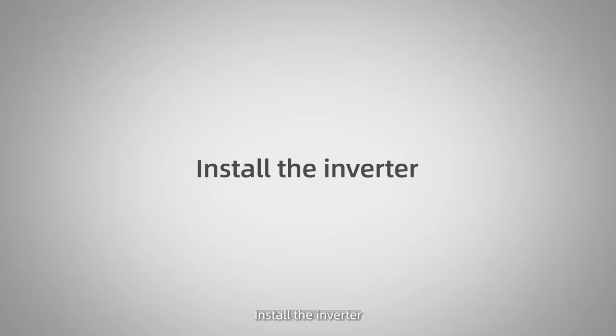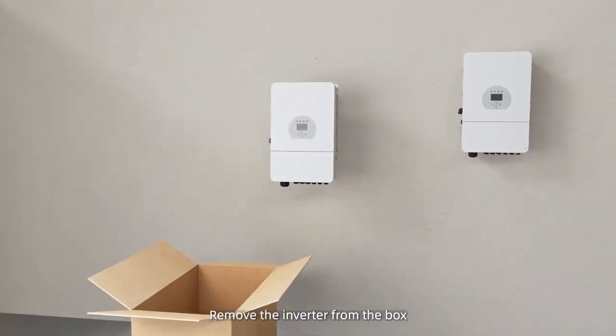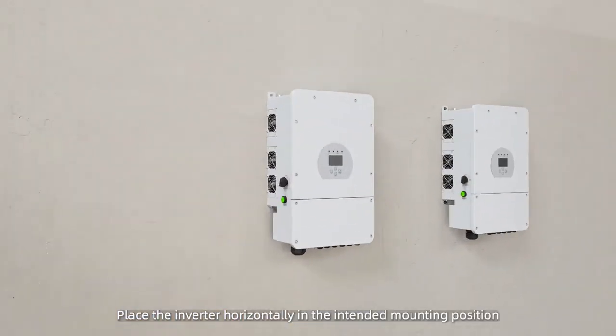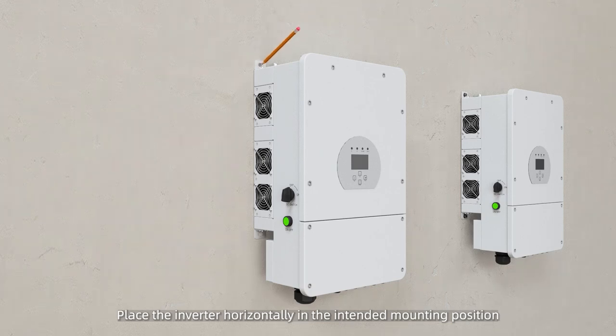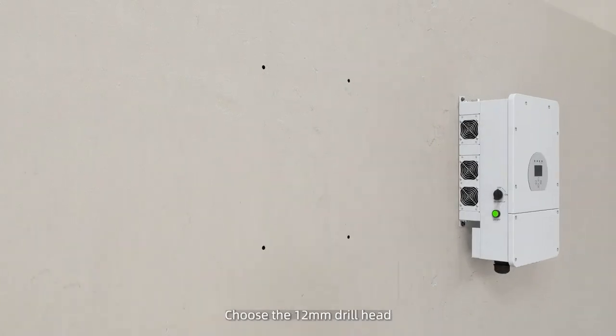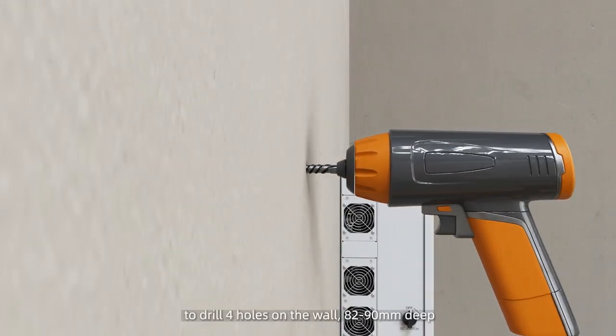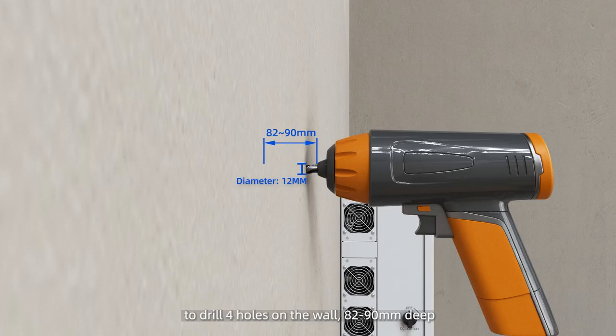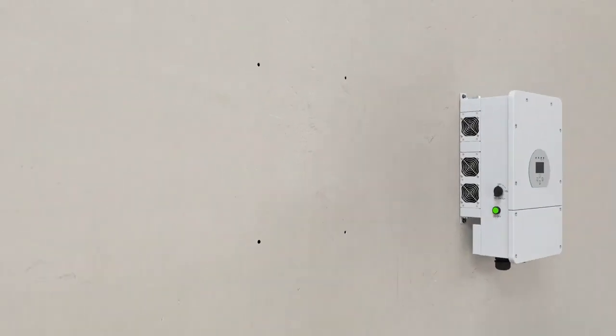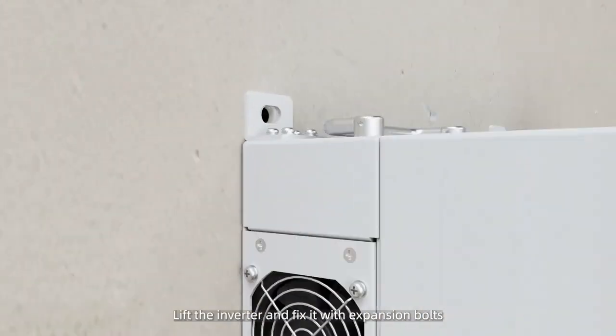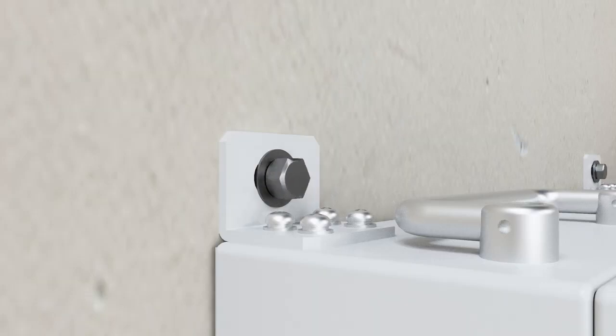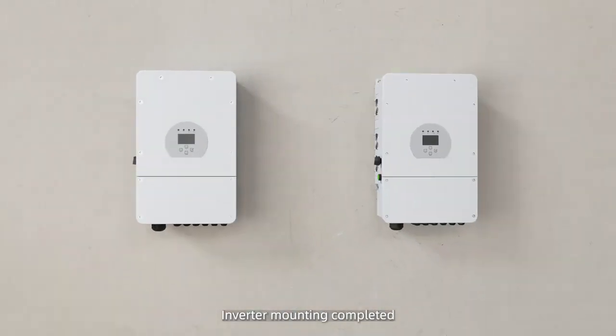Install the inverter. Remove the inverter from the box. Place the inverter horizontally in the intended mounting position. Label the 4 fixed hole positions of the inverter. Choose the 12mm drill head to drill 4 holes on the wall, 82 to 90 millimeters deep. Fit the expansion bolt into the holes. Lift the inverter and fix it with expansion bolts. Inverter mounting completed.